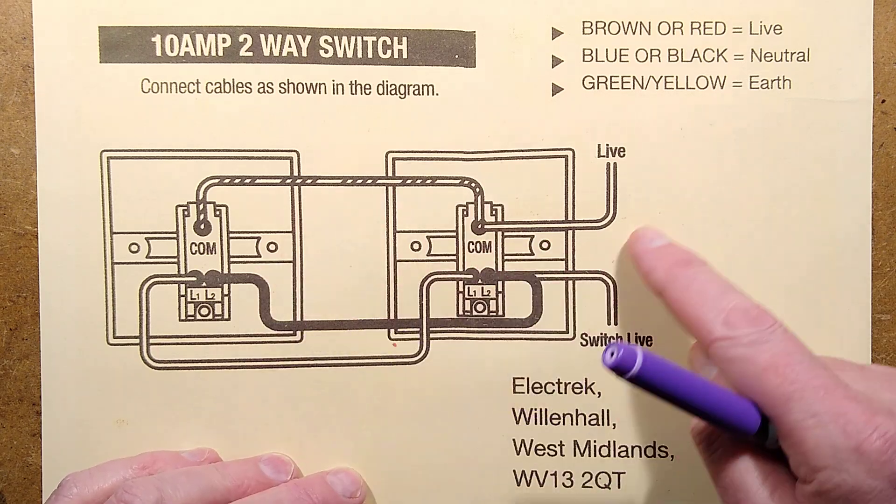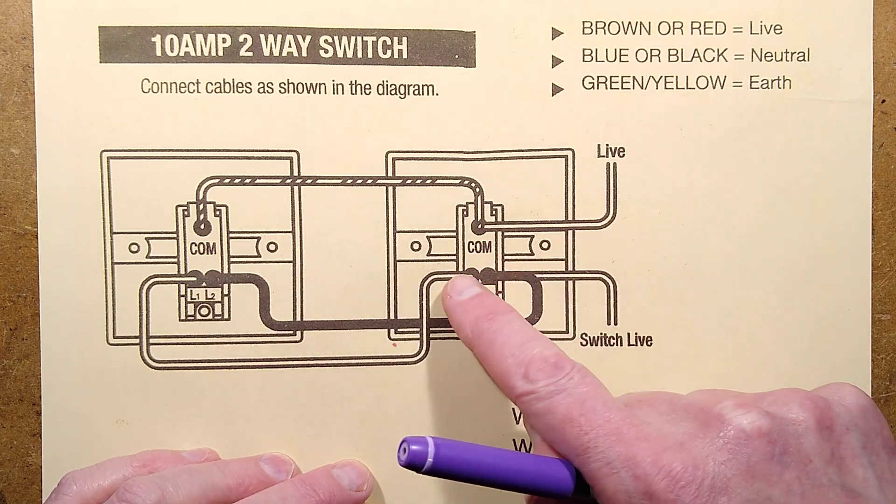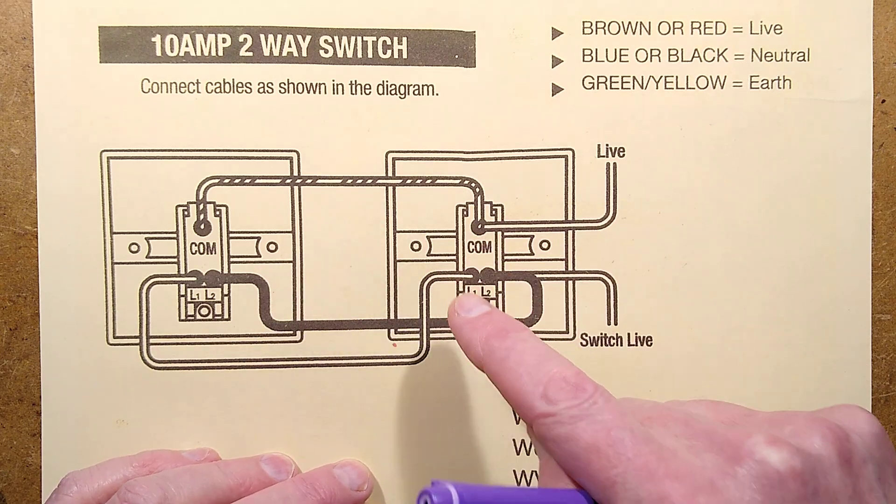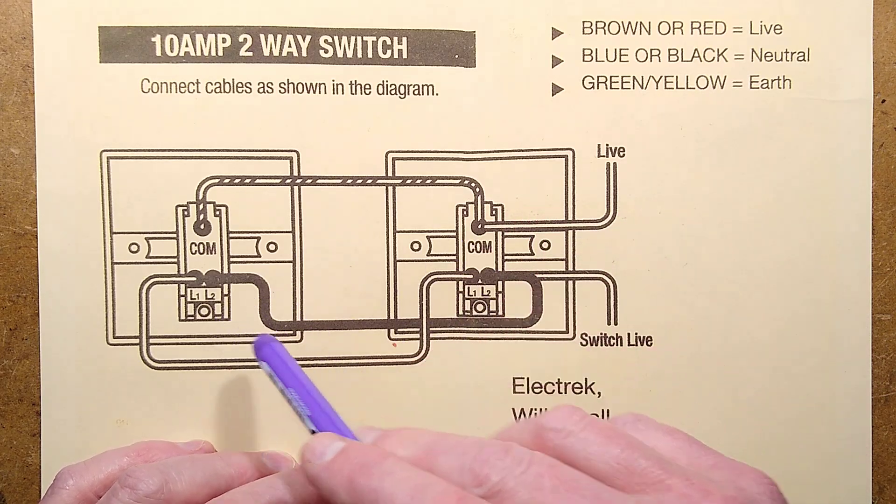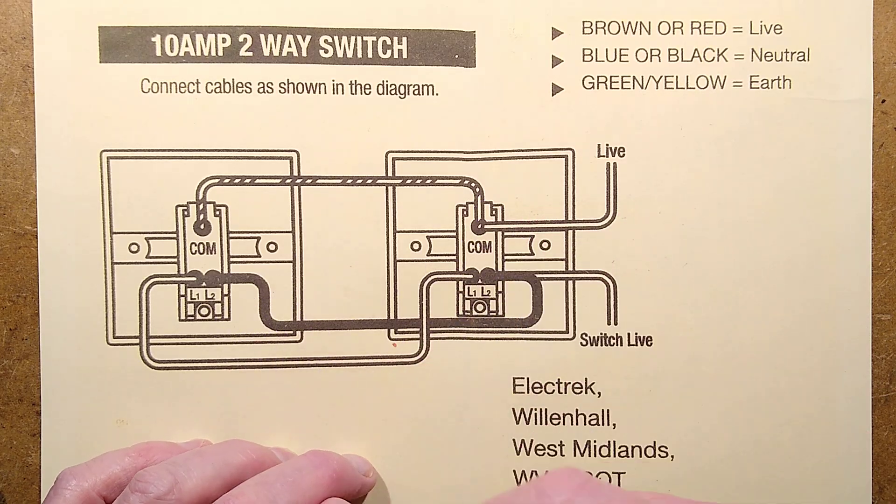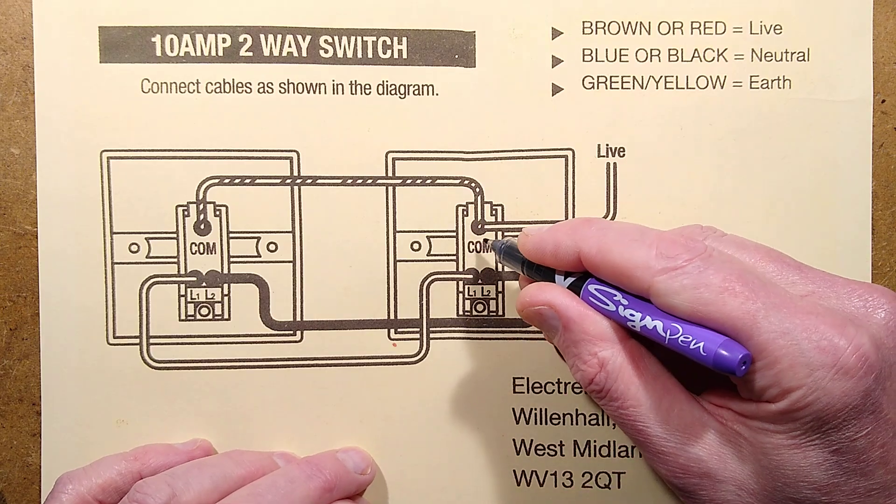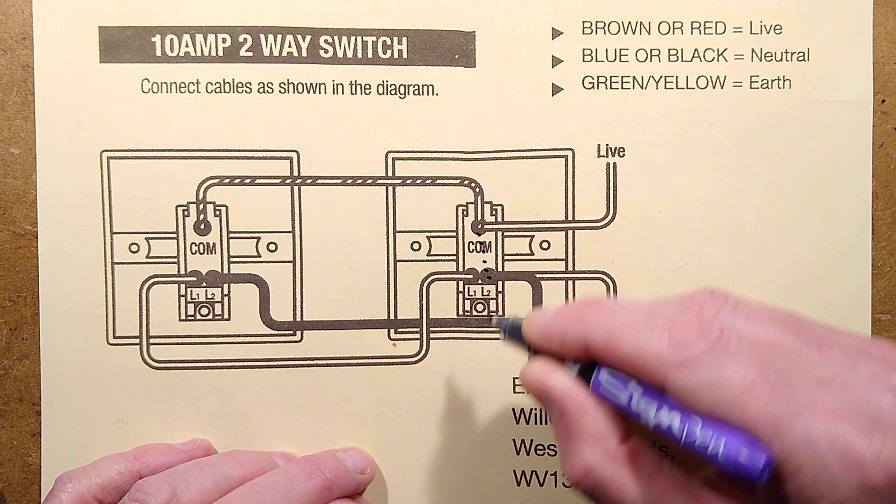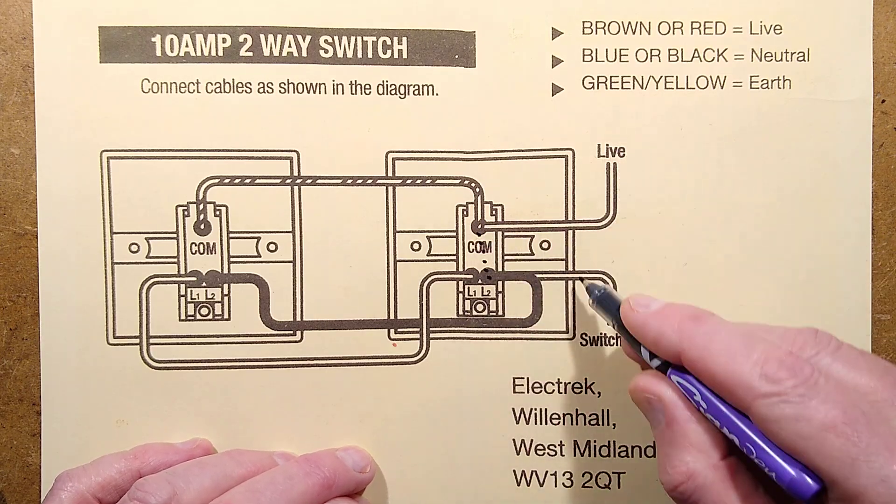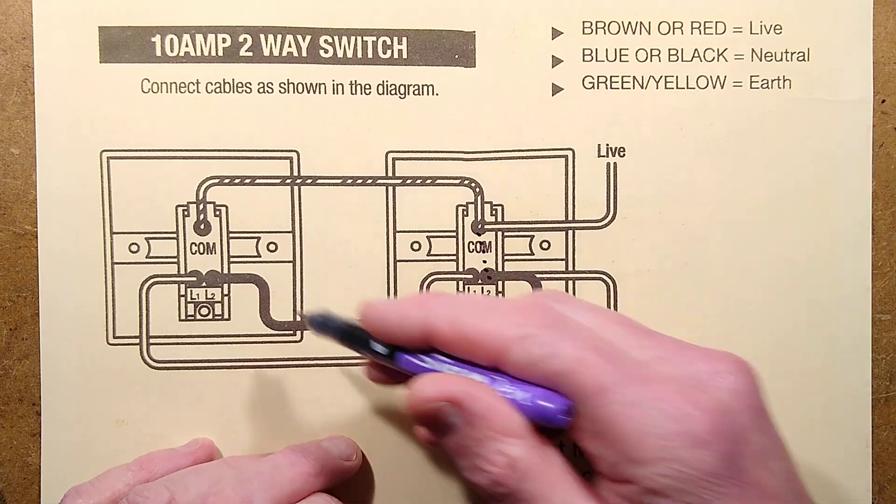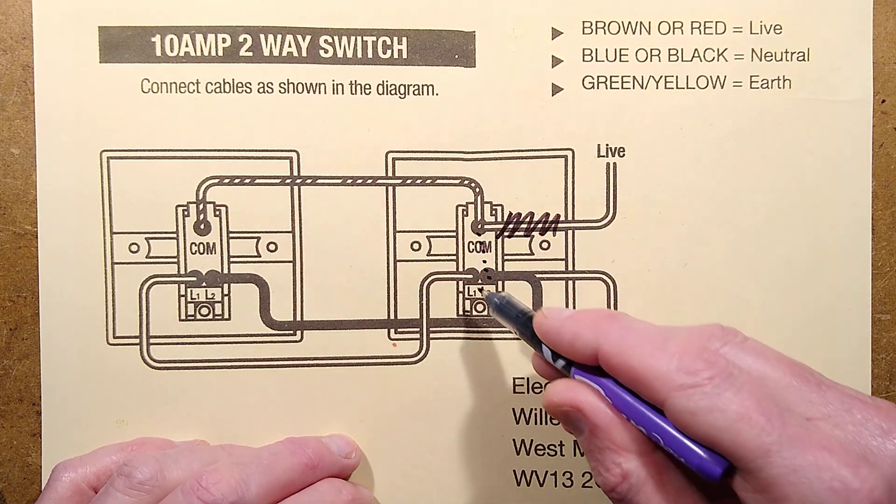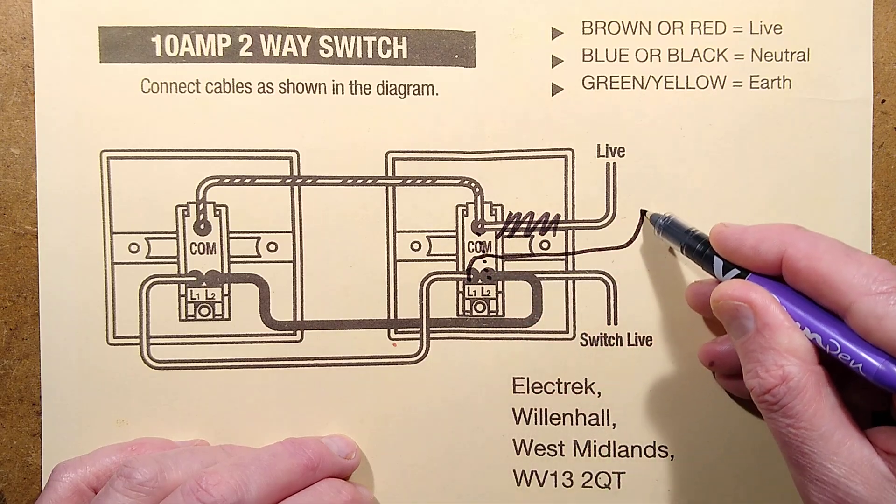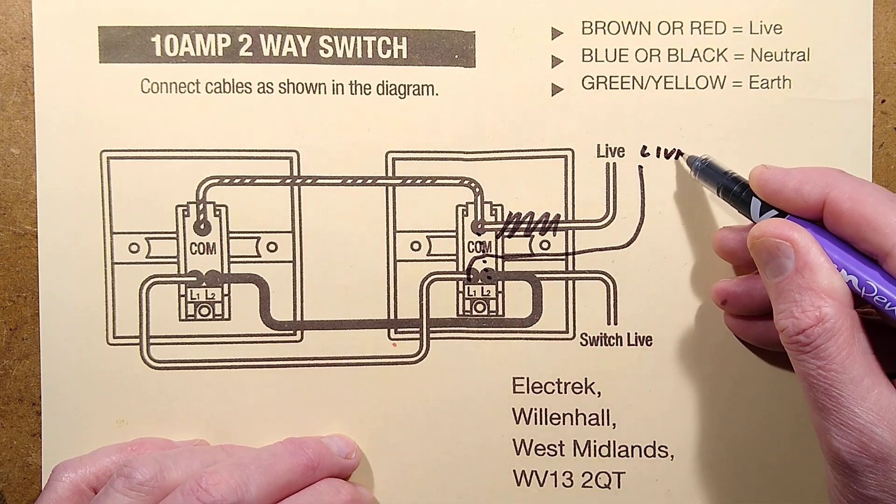While I was pondering this, I was thinking that's not right - I don't recognize this way of wiring it. There's a couple of ways you can wire this type of lighting switch arrangement, but this one is wired such that with the common, if they actually turn this switch to the on position, it will just basically bridge out the circuit, bring the light on, and that switch won't work at all. What they should have done is go from here to live instead.